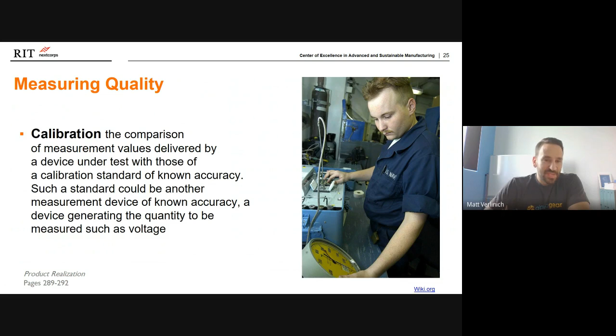But if it's a larger piece of equipment, like a granite block or a mass spec or a CNC machine, they'll most oftentimes come to you in order to put their stamp of calibration on it. And that is part of the whole quality management system that, if you're in a regulated industry, needs to be documented and tracked in your overall quality management system. Because, say, the FDA, for instance, when they come to audit you, or audit your manufacturer, they will be looking for that. So that doesn't necessarily mean that you can completely deny all responsibility for this. If you're using a contract manufacturer, they also need to be compliant.